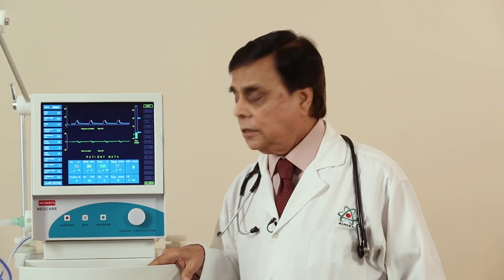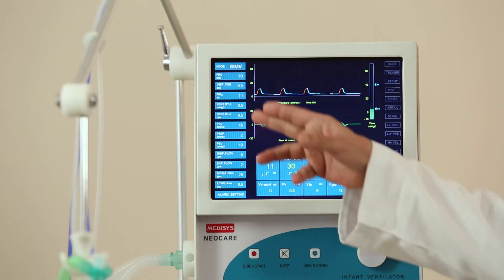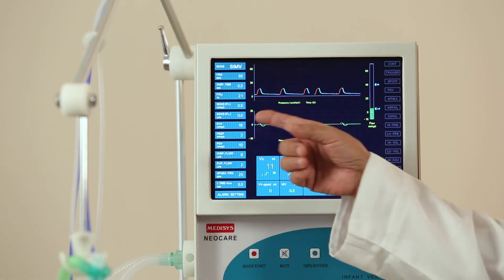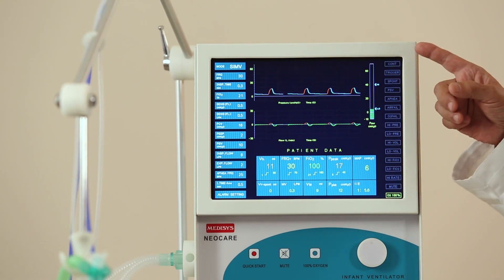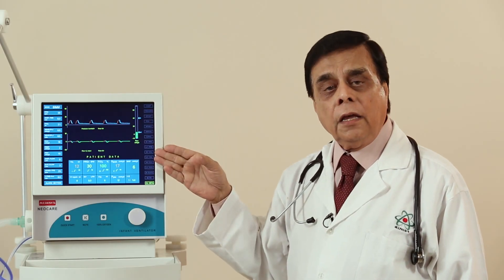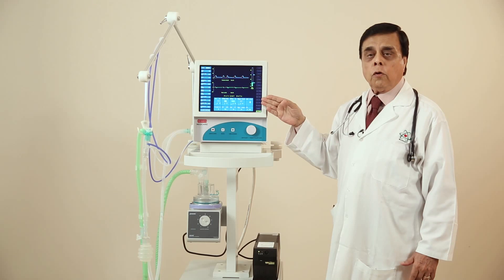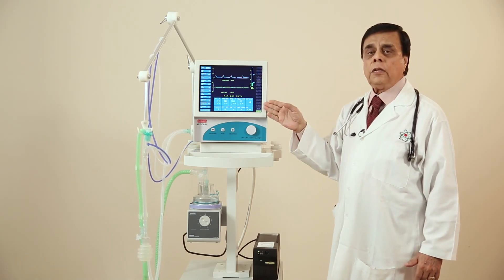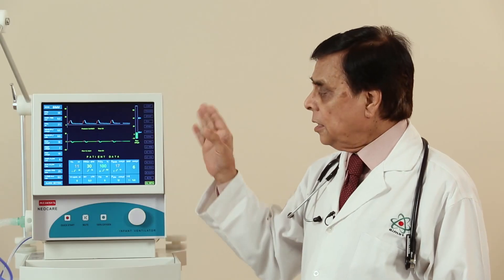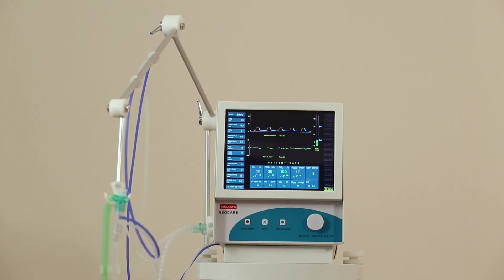The machine is ergonomically designed with an easy control system. There is a large 12-inch screen, which is very important. On one side the screen shows the machine characteristics you are selecting; on the other side are the patient characteristics. This is a unique system that continuously tells you the events which are happening, so if there is any alarm it will immediately be depicted, making your life very easy when running the system.